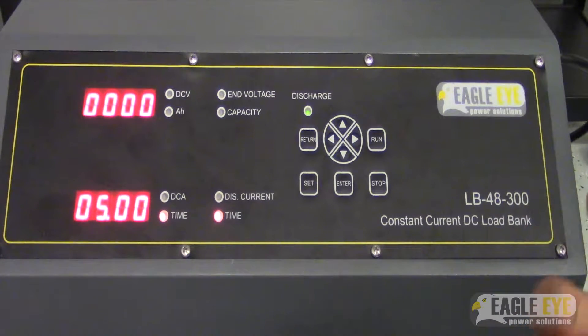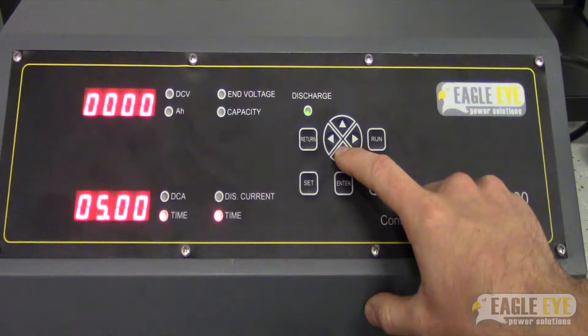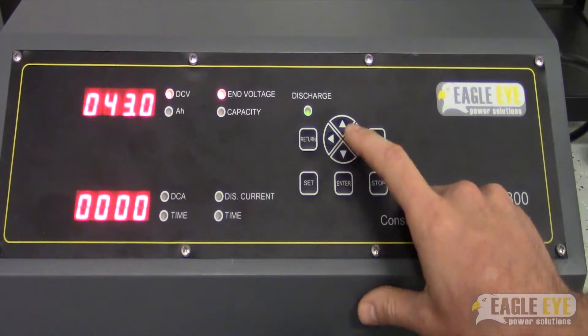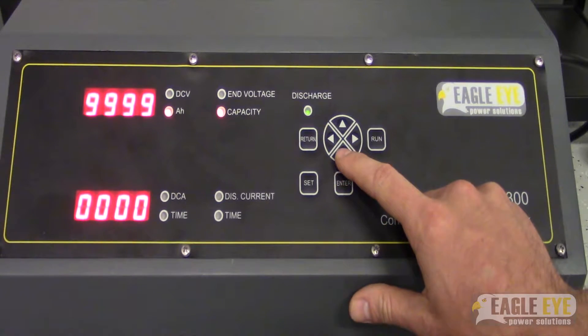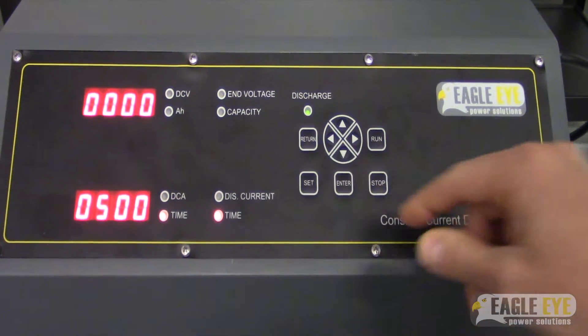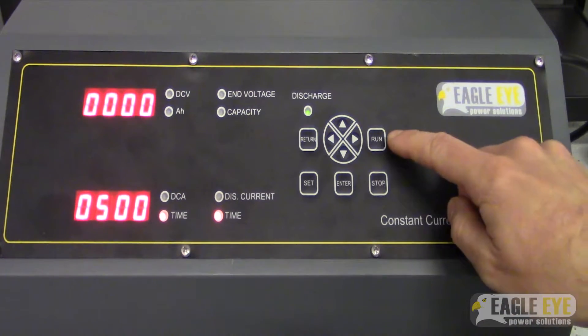But before we start, what we can do is press the down arrow key and go through all of our settings to make sure that everything is set to where we want. So we have 43 for end voltage, 9999 on our capacity, 40 amps for our discharge current, and 5 hours for our test. Everything looks good here. We're ready to now start the test, so we can press run.